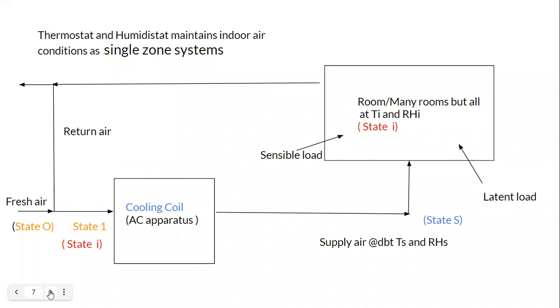So this would clarify what is a single zone system. For example, there are a number of rooms over here, and there is a thermostat and a humidistat which would maintain and give the signals to the cooling coil so as to maintain it at a particular temperature Ti and a particular relative humidity RHi. You see that there is a single system, single supply duct and a single return duct.